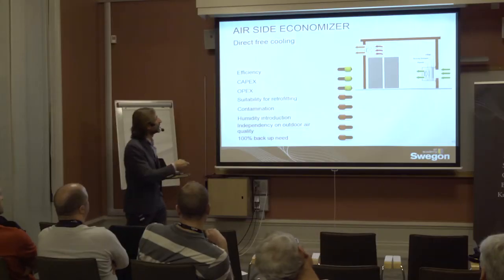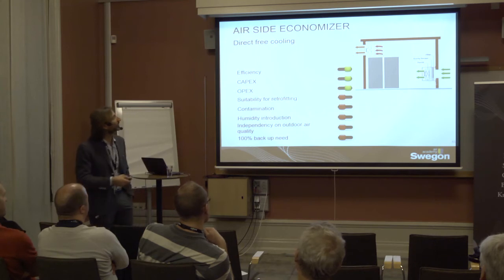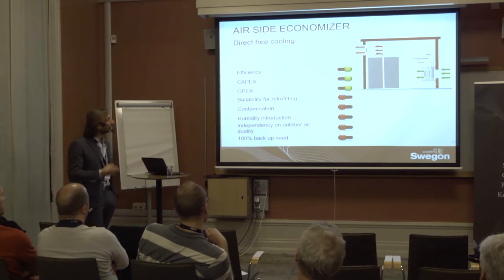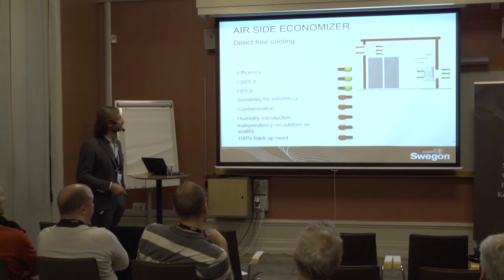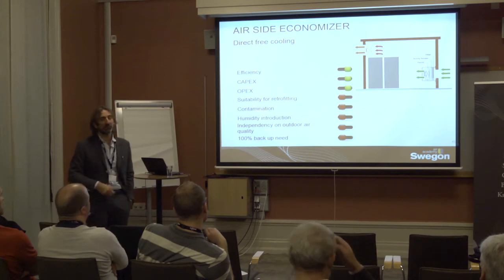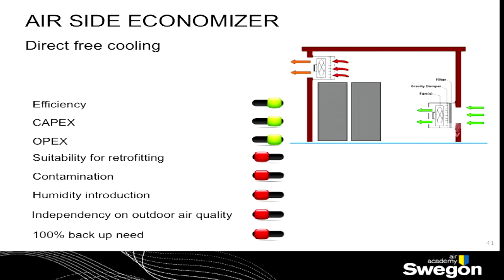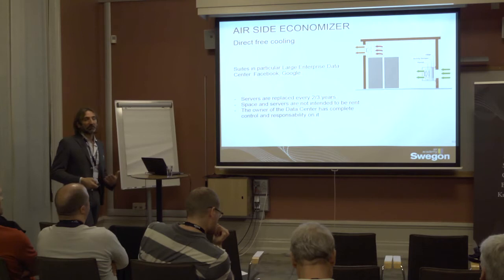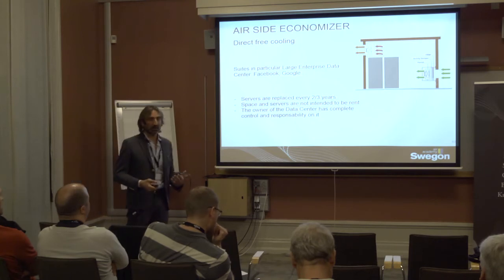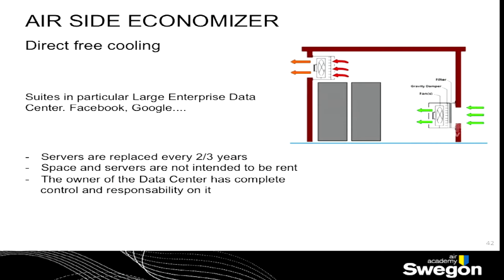Sometimes I can avoid the extraction because I can put, let's say, a pressure damper here and move the air only with these fans. But if we consider the contamination, the retrofitting, the humidity introduction, the strict control of the indoor air, it is of course not the best solution. Where is it mostly used? It is used where the servers are changed quite often, are renewed quite often.